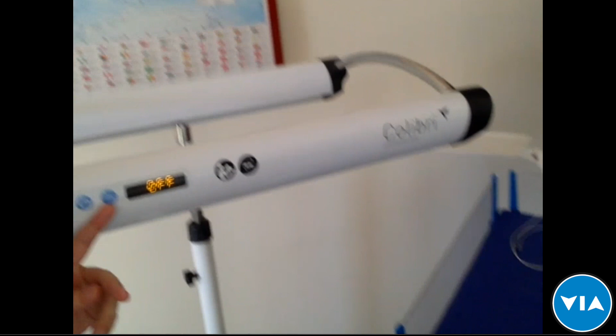If you can just touch on that again quickly, talking about the difference in intensity or specification of the bulbs for Colibri versus Firefly, knowing that one's more single-sided, the other one's double-sided. Okay, so again, the LEDs that we use are exactly the same, which means the light spectrum with the peak are exactly the same for both devices. The only difference is that in Colibri, you can regulate the light intensity because we have two modes, standard and intensive, while in Firefly, you have only single mode, just intensive. And Firefly have bottom and top lights, while this one has only light from the top, which also affects the effective treatment surface area.